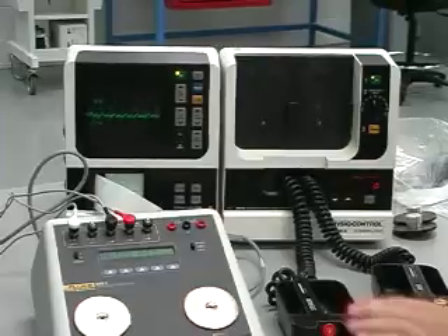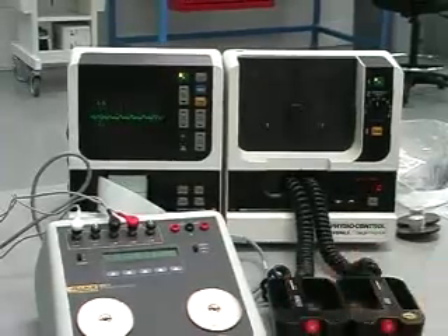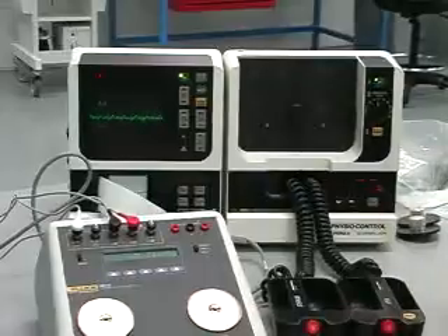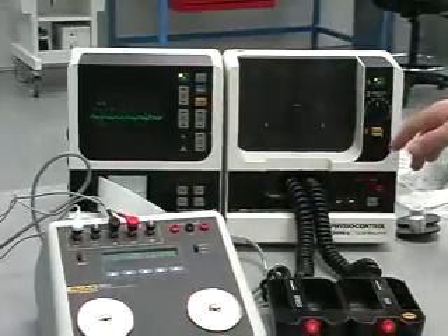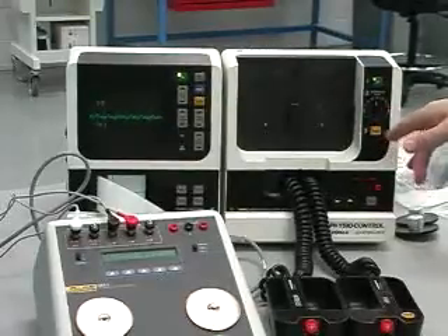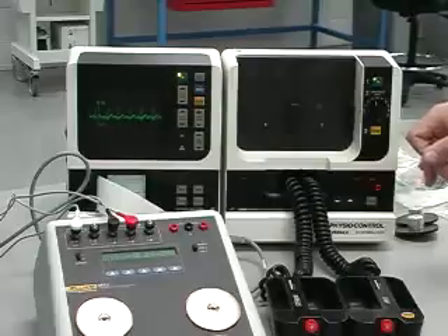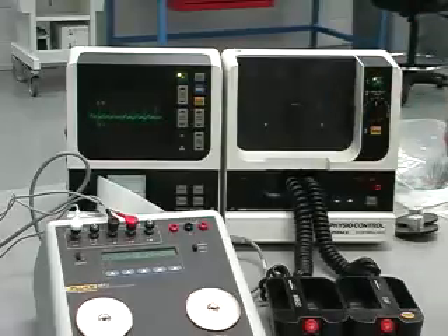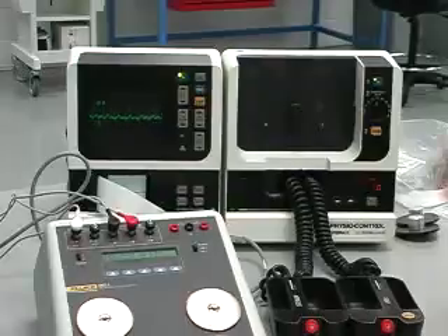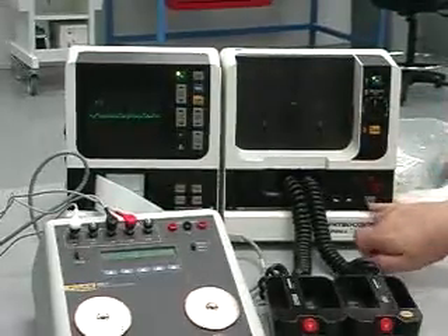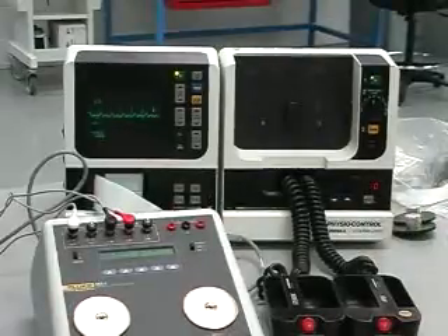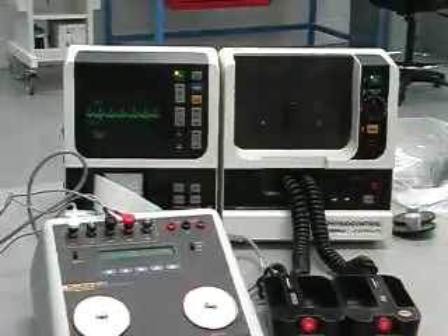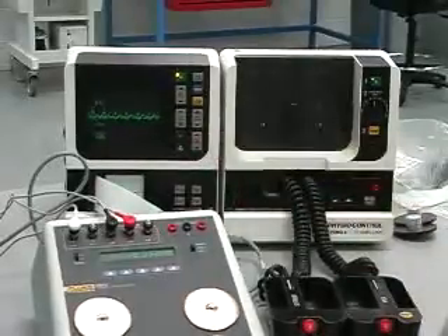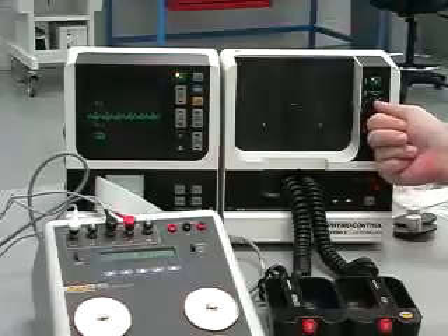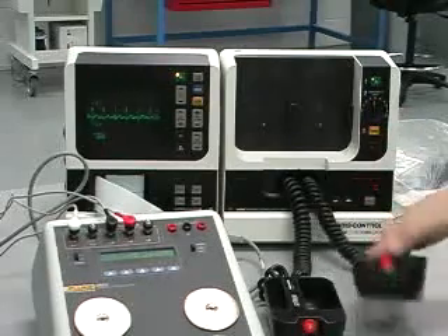Okay, so at this point, whenever you run the test for the synchronization, after you discharge, the defib will automatically revert back to an instantaneous discharge mode of operation. So now it's ready to go for emergency use. And if you simply wanted to run the synchronization test again, just re-hit the sync button. Marker comes back up, and again just pop up the amplitude, set it at an energy. Typically the tests are done under 100 joules, and just charge it up.